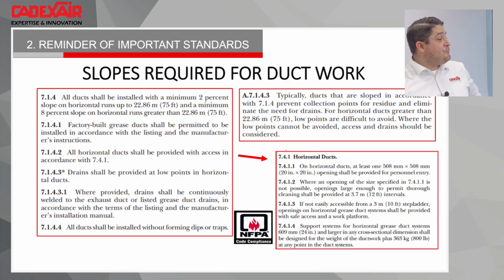So, yes, Mike? Yeah, sorry to cut you off, but I have a question from another participant really related to this topic. Is it mandatory to install a valve when we have a drain in a sloped duct? No, you can only put the cap. It's just to be able to be drained. But I will say for a kitchen exhaust hood guy, you prefer to have a valve. It's easier to work with, and often the cap, when you just put it back, if you don't screw it correctly and you don't put any Teflon or anything like that, it can drip. So I think a valve will do a better job. But I will say a cap will still be as per law.